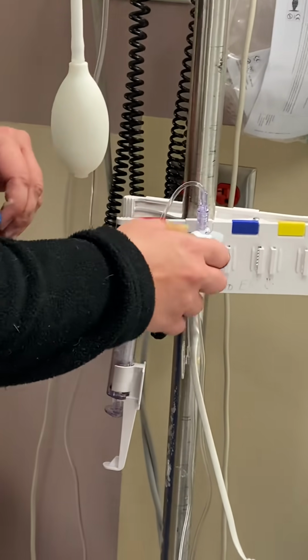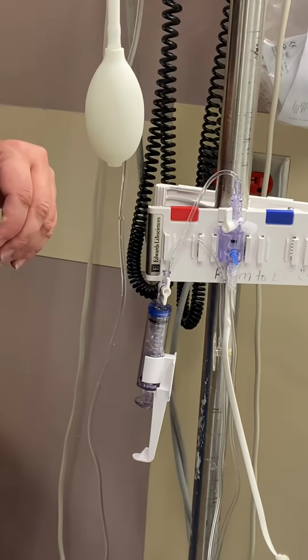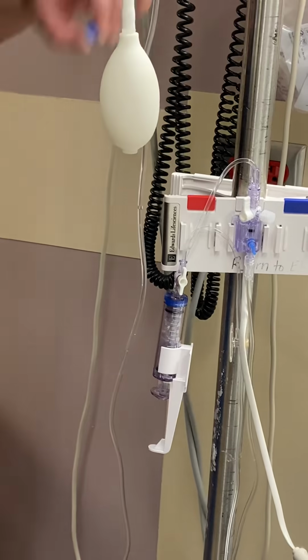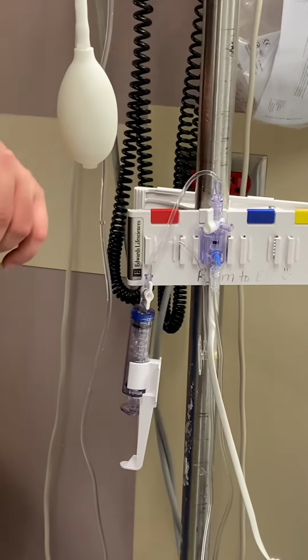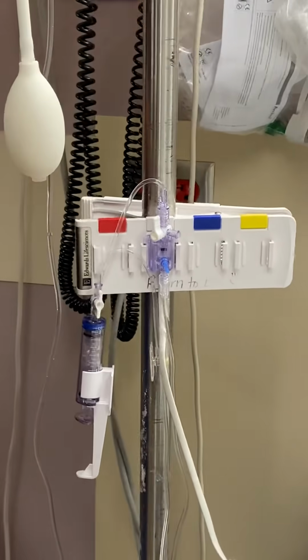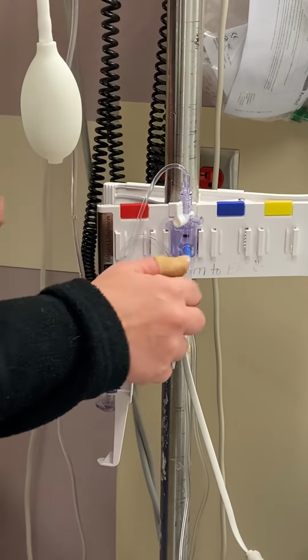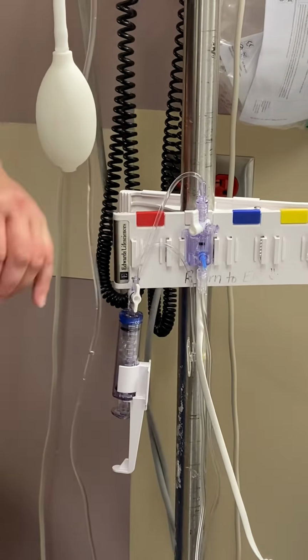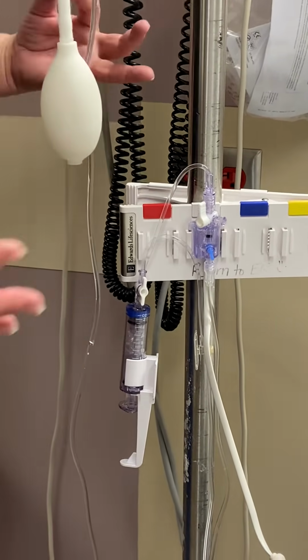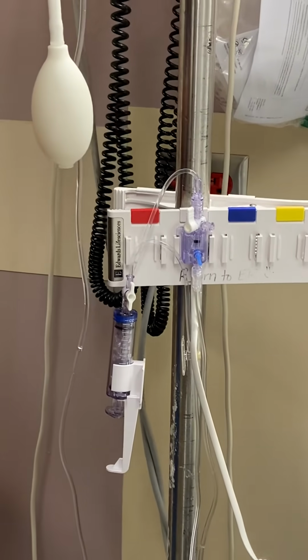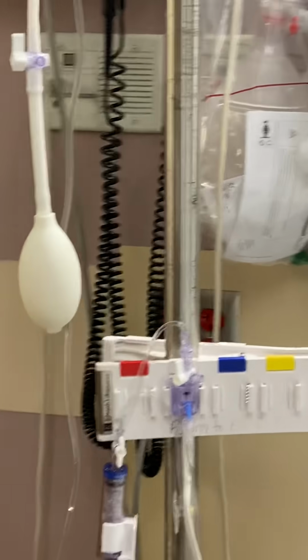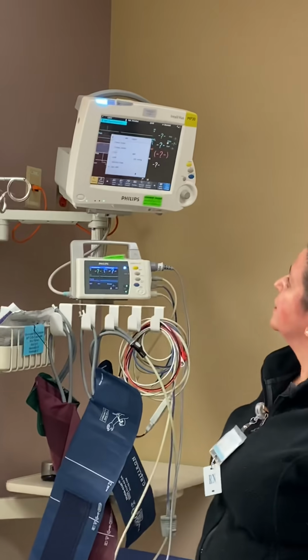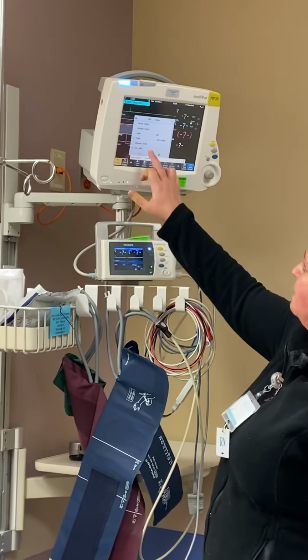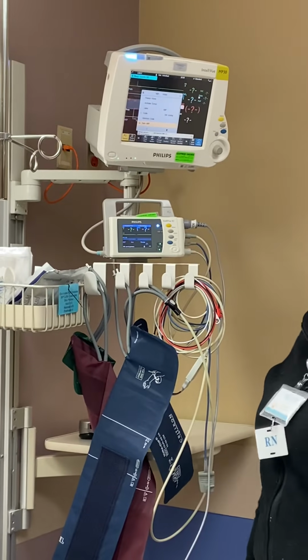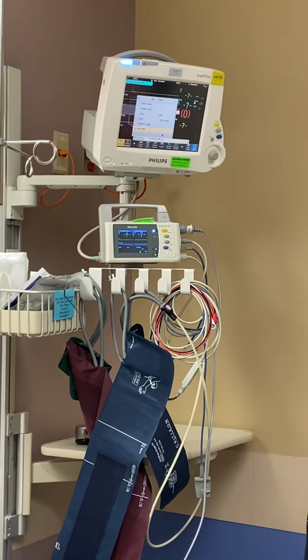So to zero my system, I need to open the system up to the atmosphere. So I'm turning my valve up to the atmosphere. I'm going to take my white vented cap off. That can be thrown away. And then I'm going to purge the air out of this 0 port by pulling on my pigtail. So I've gotten all the air out of that. And now my system is open and I'm ready to zero it. So I'm going to need to go back to my monitor. And I'm ready to zero. So I'm going to hit my monitor and it says 0 ABP. I'm going to hit that. It's going to zero my system and I'll get an alert once it's done.